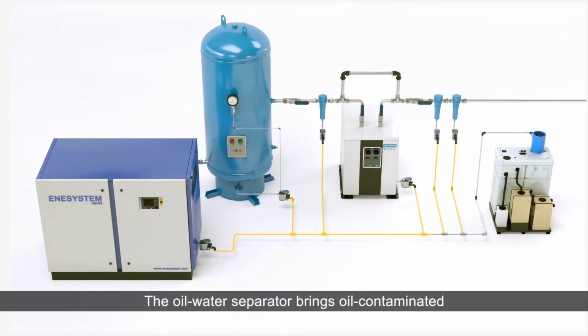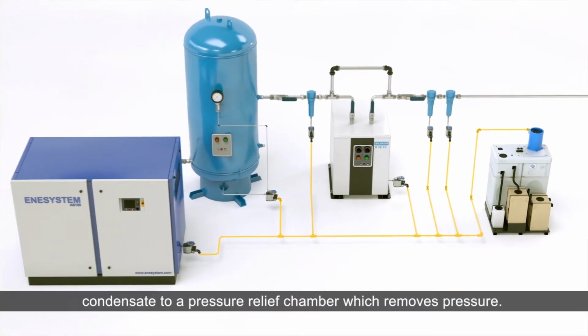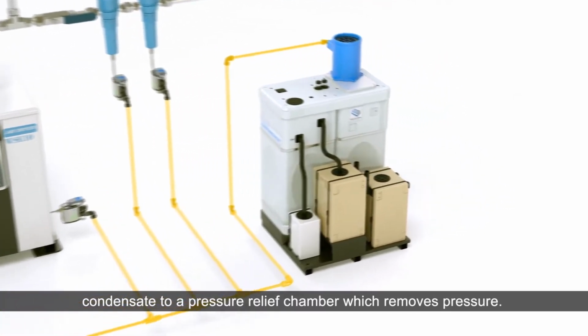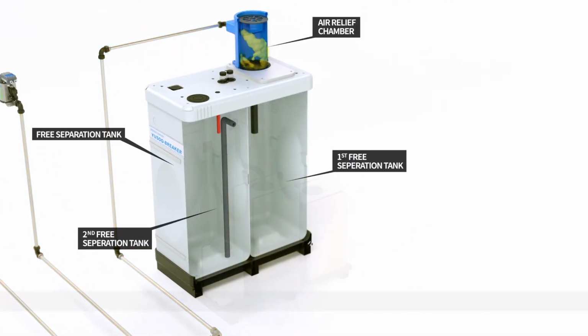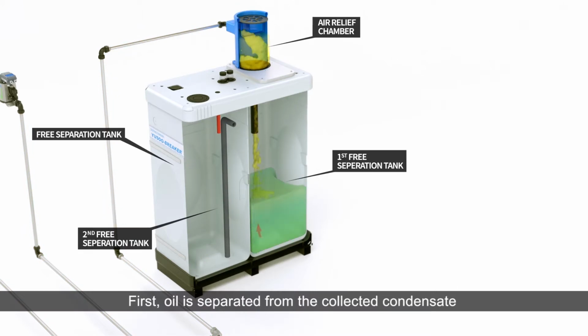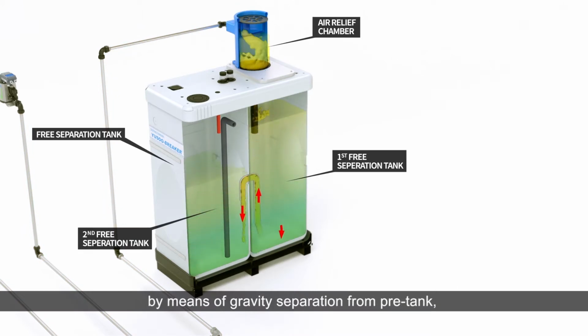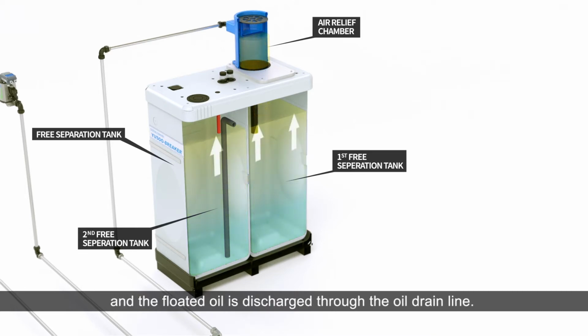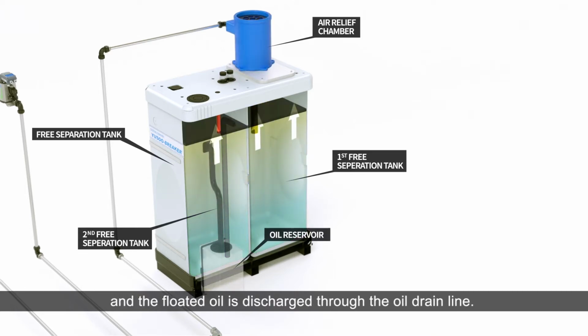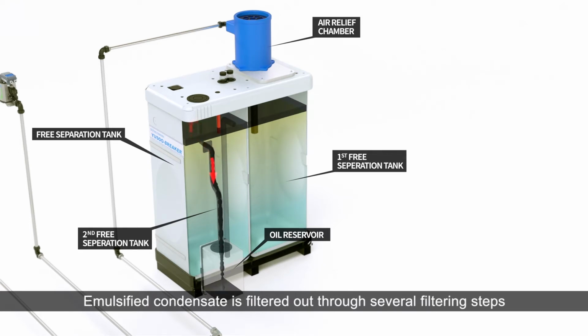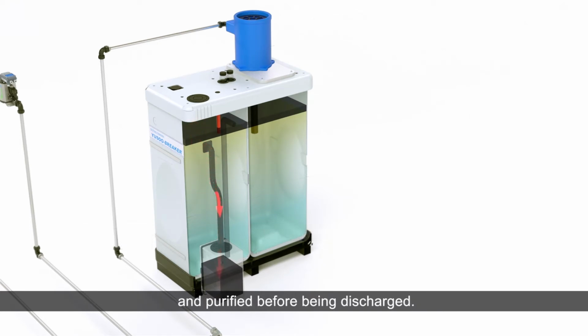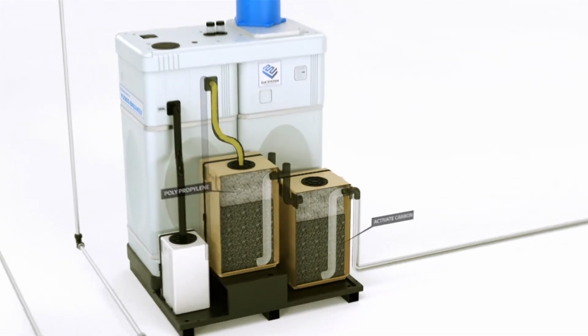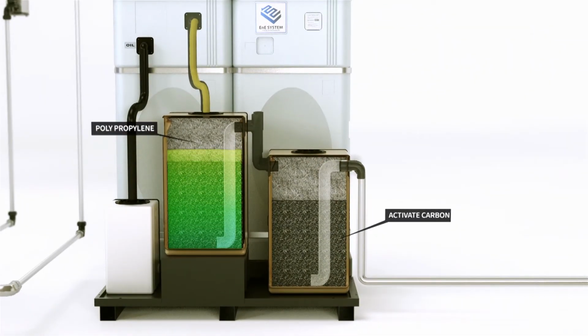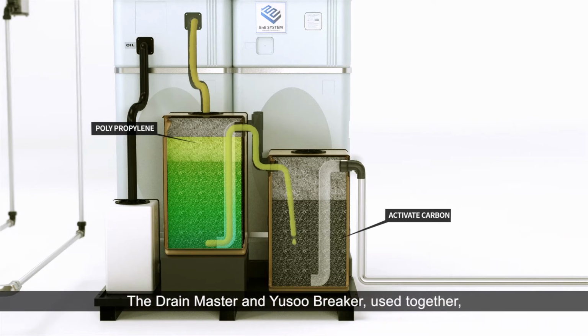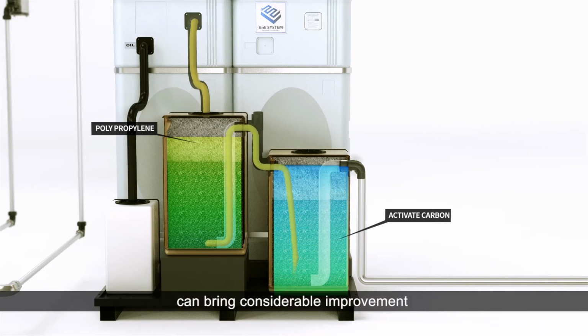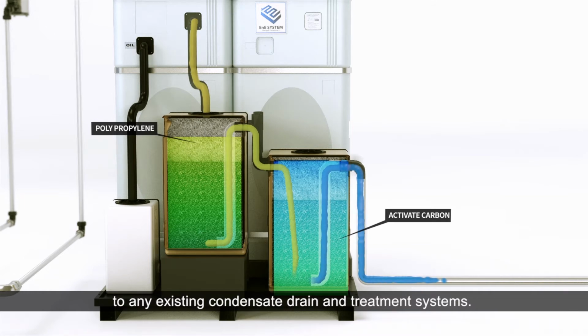The oil-water separator brings oil-contaminated condensate to a pressure relief chamber, which removes pressure. First, oil is separated from the collected condensate by means of gravity separation from the pre-tank, and the floated oil is discharged through the oil drain line. Emulsified condensate is filtered out through several filtering steps and purified before being discharged. The Drain Master and oil-water breaker used together can bring considerable improvement to any existing condensate drain and treatment systems.